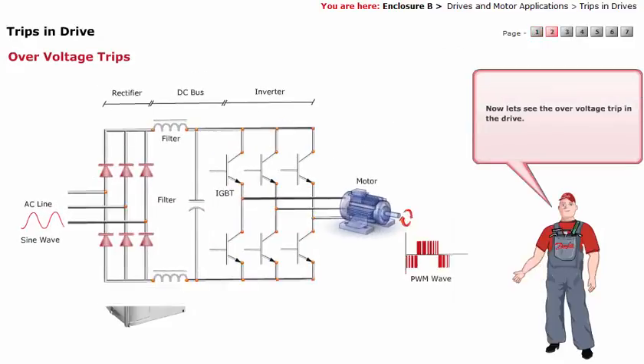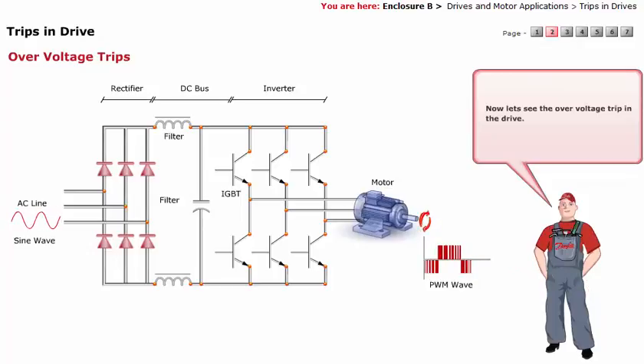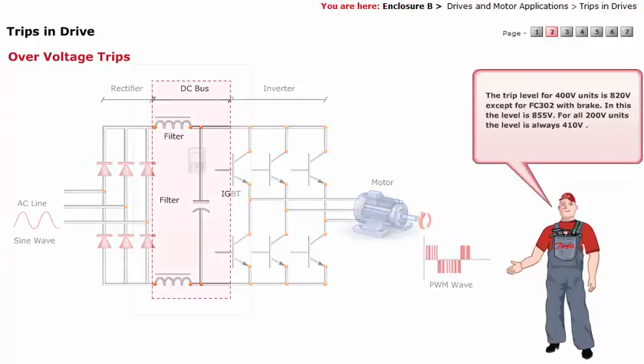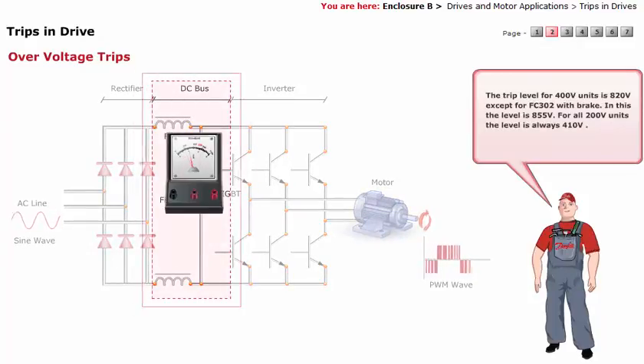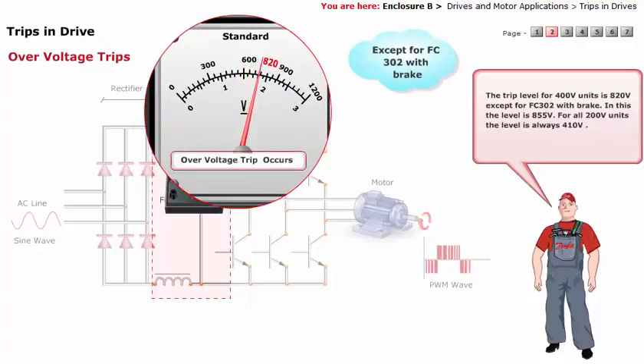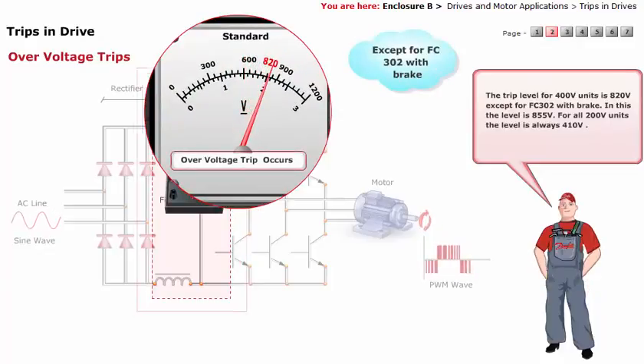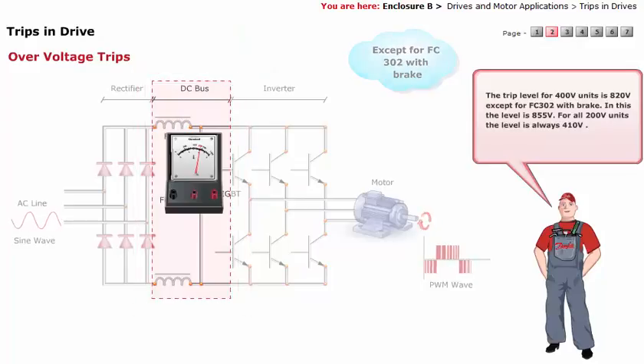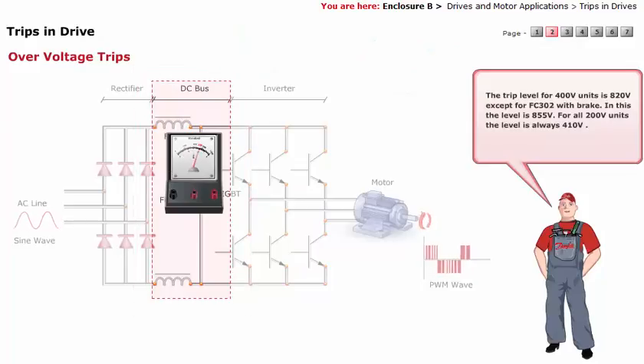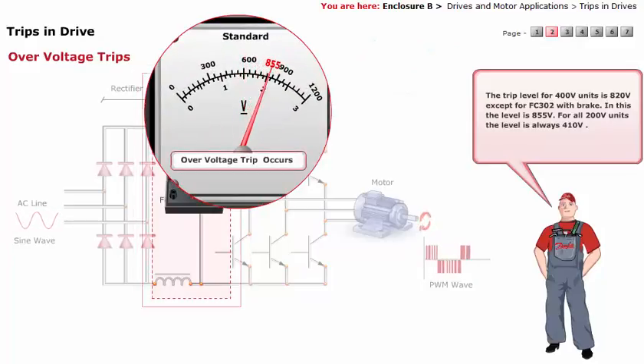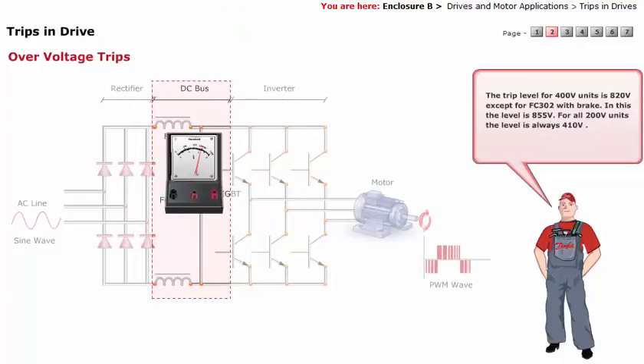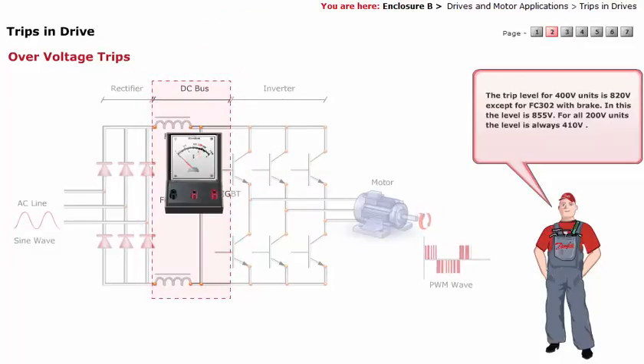Let's see the over-voltage trip in the drive. The trip level for 400V units is 820V, except for the FC302 with brake, where the level is 855V. For all 200V units, the level is always 410V.